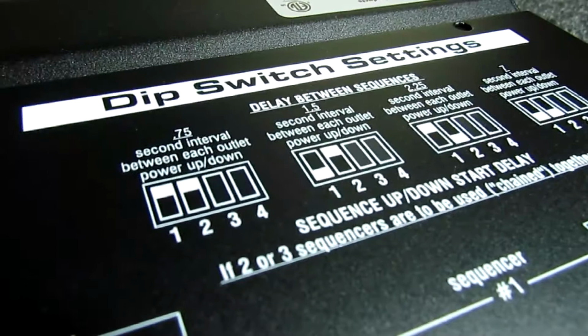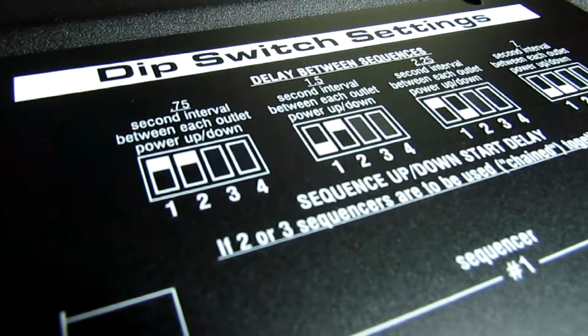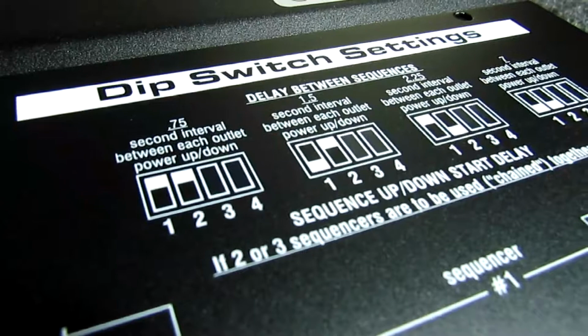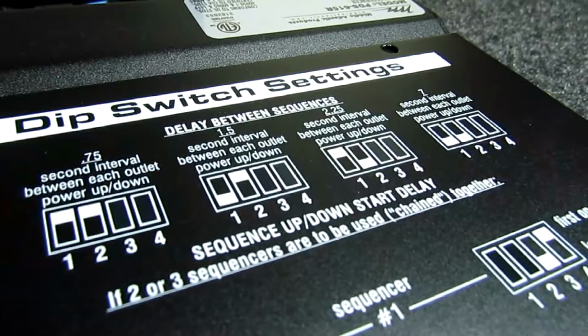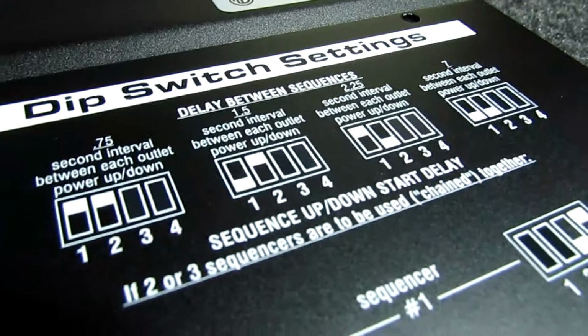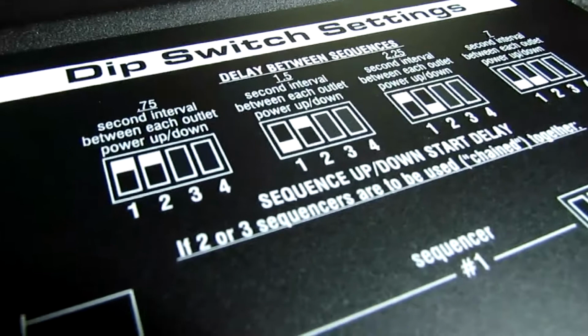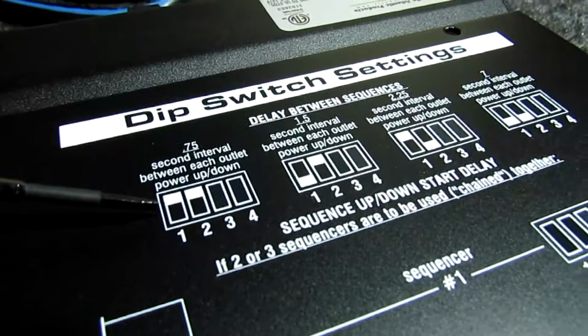Okay, here the first two switches. So I guess I should start. So these are the dip switch settings, obviously. You'll notice the very first two have to do with the time interval or the delay between sequences. Now, just dip switches 1 and 2 there, you can see when 1 and 2 are both flipped to the up position, we've got a 0.75 second delay.